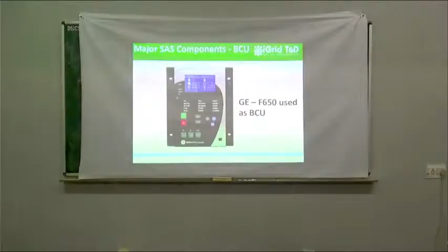The first main thing, if you observe, is that for every bay we have what is called a bay control unit. For example, I have just stated GE-F650. Similar to this, we have BCUs from different companies like ABB, Siemens and others. They have their own bay control units. So what is the objective of this bay control unit? Basically, it is used for controlling the switchgear. That means if I want to open my breakers or my isolators, I can do this control operation using the BCU. For every bay we use one separate BCU. So whenever I want to do a control operation, I do it using a bay control unit.